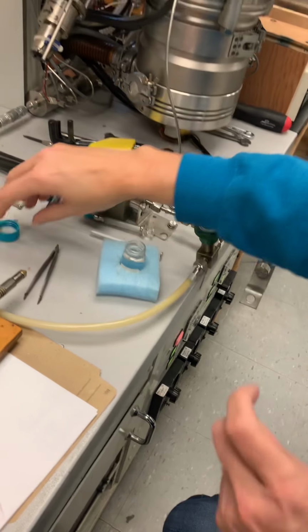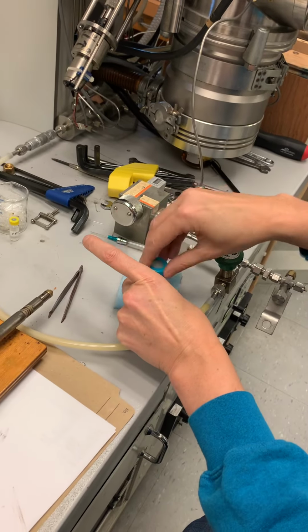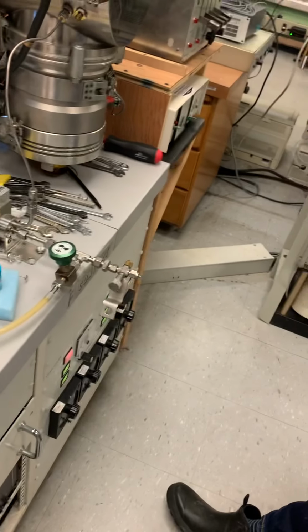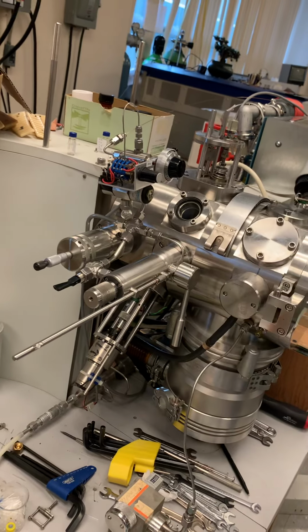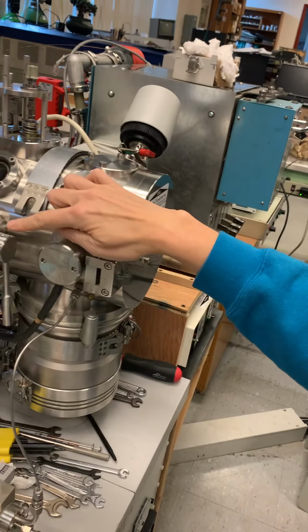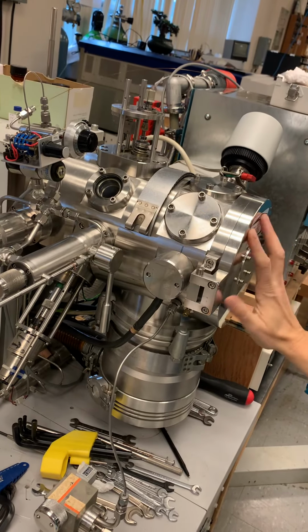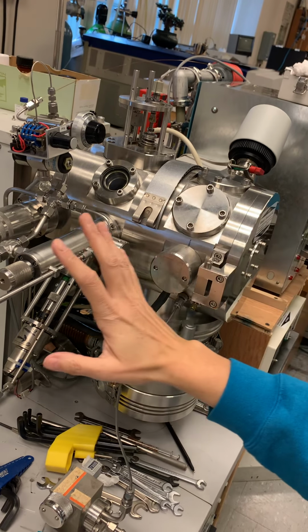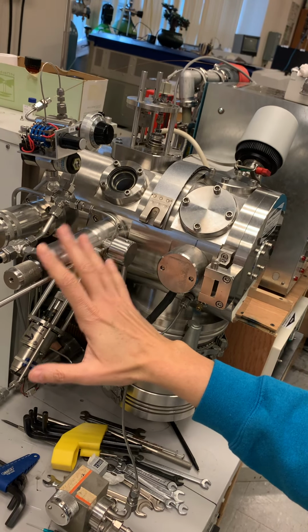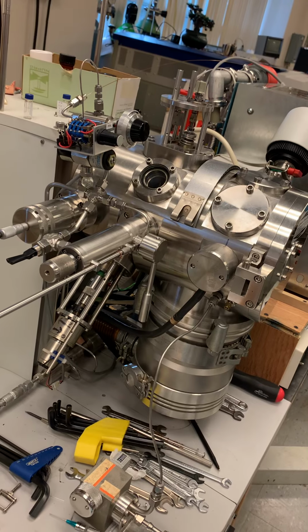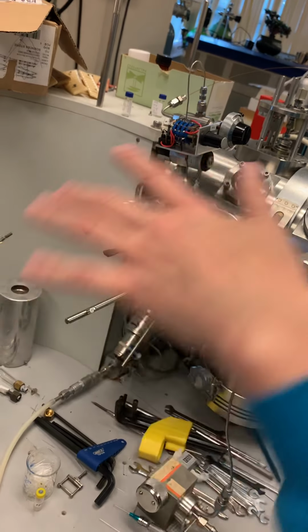And now I'm going to break the vacuum system. So there are two sections to doing this. One is the probe inlet here, and then you have the actual source, and there is a gate between the high vacuum area and the roughing pump vacuum area here. So to break that vacuum, I need to turn off the roughing pump, because if I just pull the tube out, the poor roughing pump is going to try and suck air out of the whole lab.